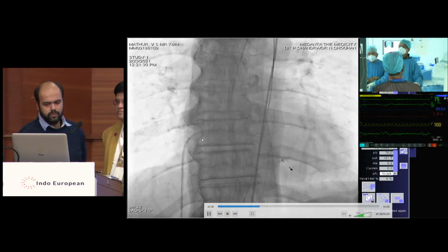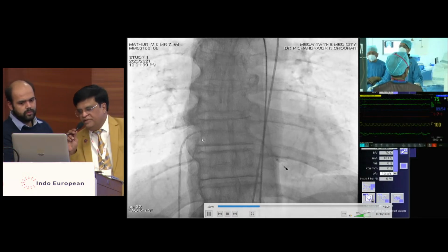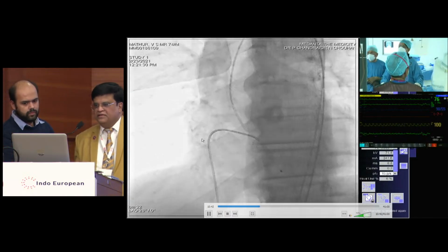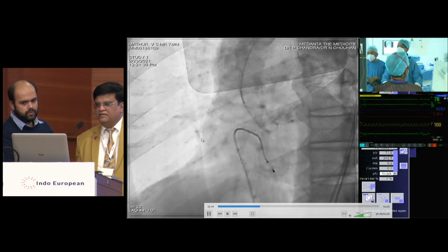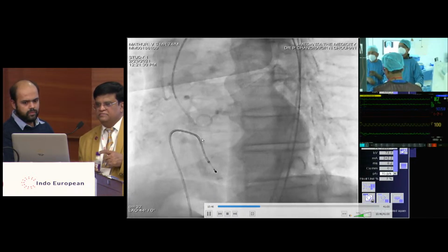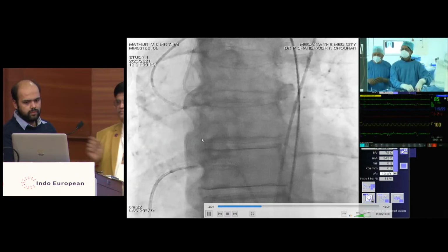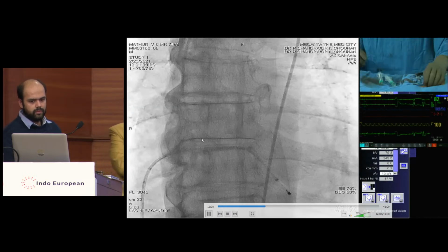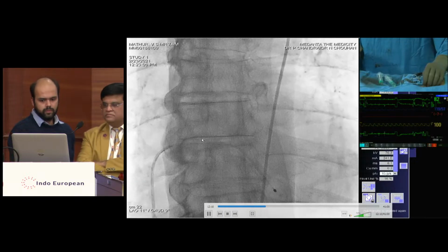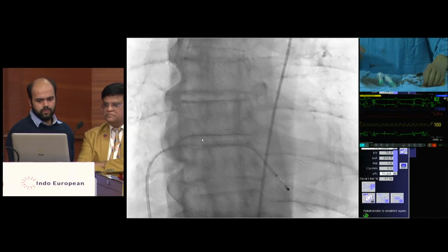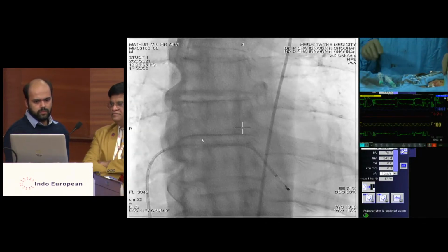So we can check whether the patient captures these, so that is perfect. So check at higher rates, because sometimes at higher rates it can miss. The temporary pacemaker lead is always checked there. I am going to check it at 120. Still it is 1:1, so we are fine. We are okay, it is not going out.